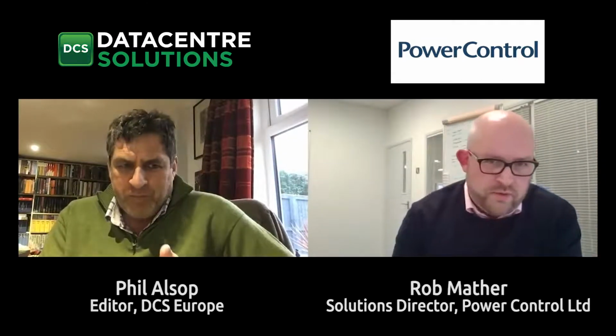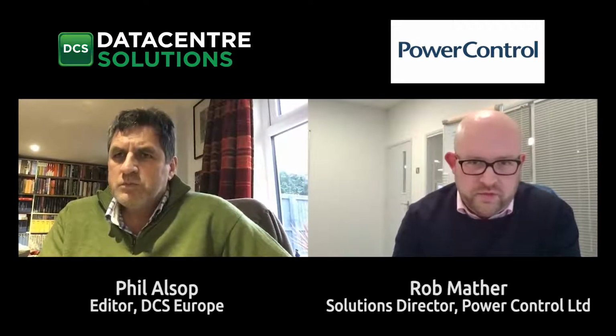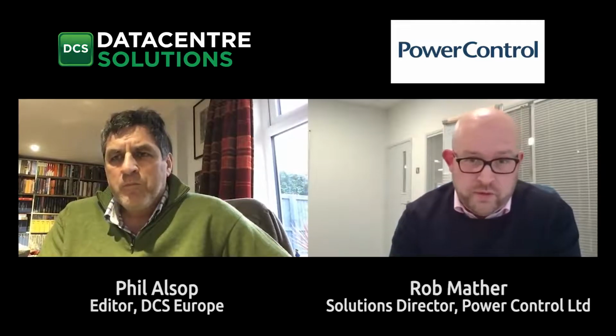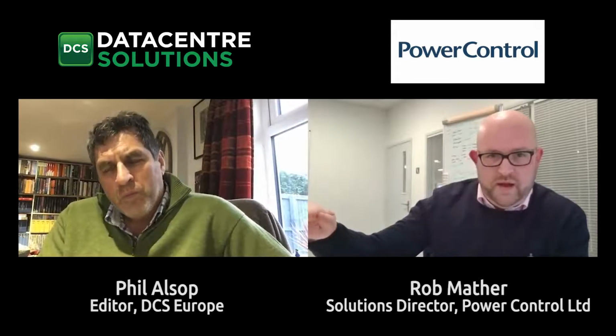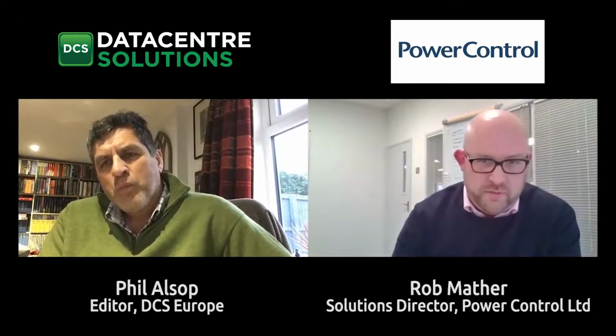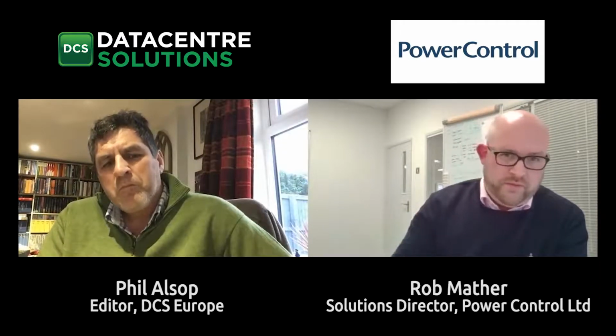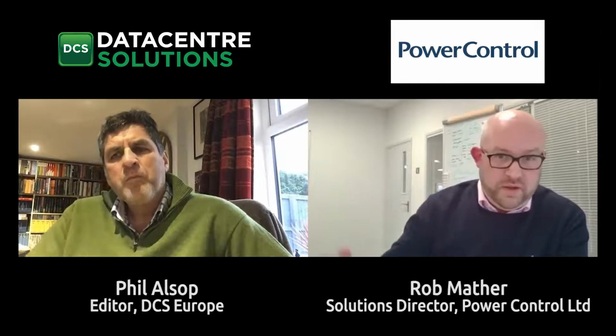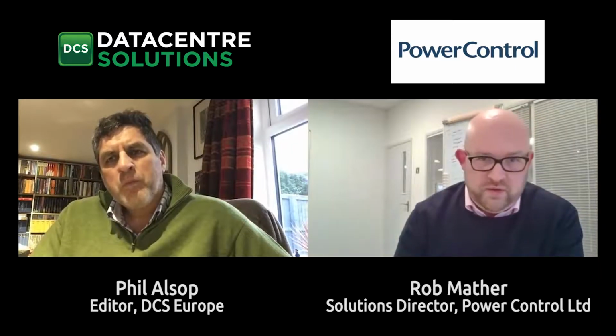The main problem with fuel cells is scaling them up to any meaningful power for data centers. We've had probably more exposure to them than most other UPS companies. So we've been working with companies and they actually needed a UPS with the fuel cells to make them work. The biggest problem that a fuel cell has got is if it's a steady amount of power required, it's fine. But if it's a constantly changing, fluctuating power requirement, the fuel cell needs to ramp up and ramp down, and it can't do it immediately. So you normally end up having to have a UPS or battery or something there to take the peaks and the dips. So the fuel cell's got a steady, constant requirement, then the UPS takes the rest.